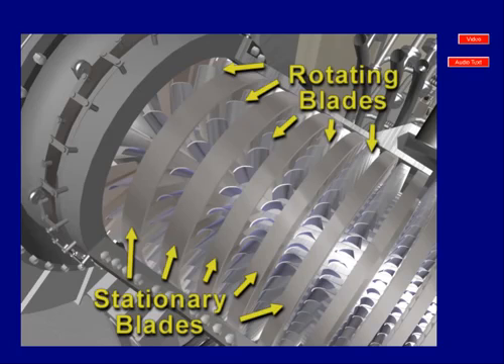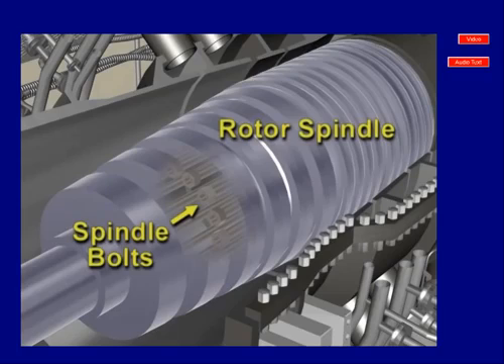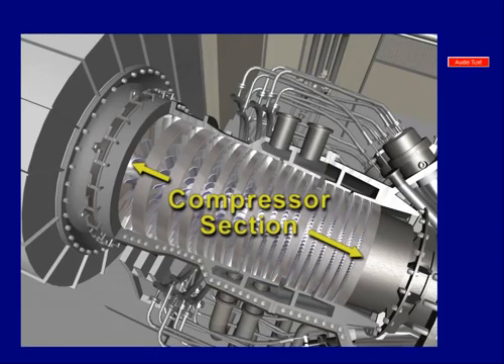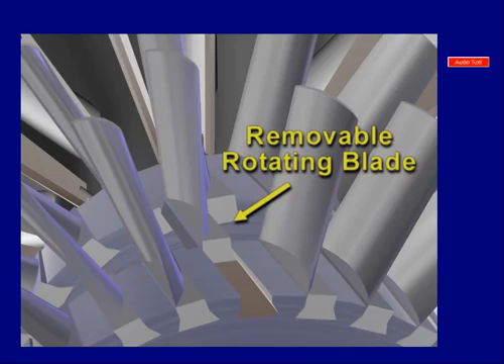Stationary blades, or blade rings, are positioned before each of the sets of rotating blades. The positioning of these stationary blades efficiently directs the air to the oncoming rotating blades. The rotor is made up of a bladed compressor spindle and a bladed turbine spindle that is bolted together to make a single shaft. To view an animation of the compressor, click on the button provided. The compressor consists of 16 rows of individually removable rotating blades.